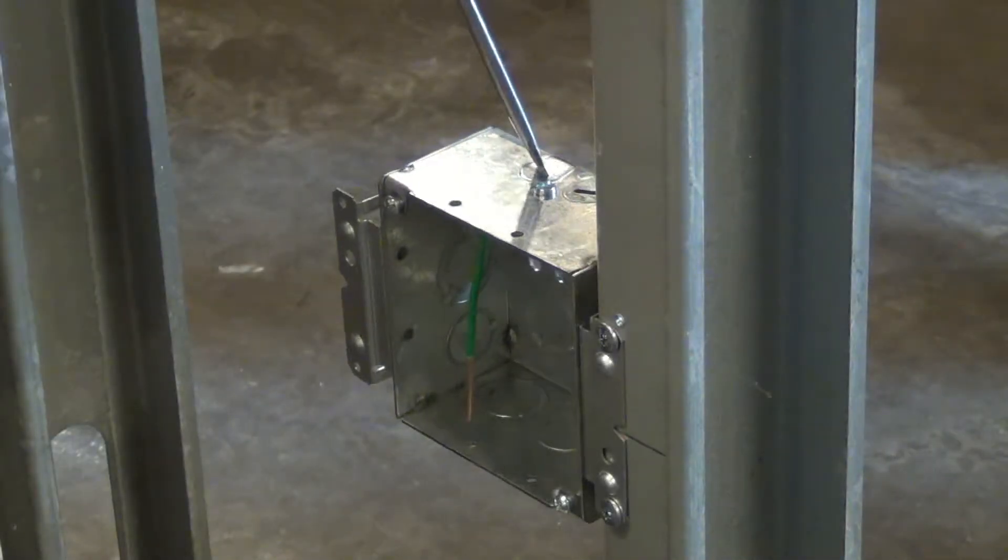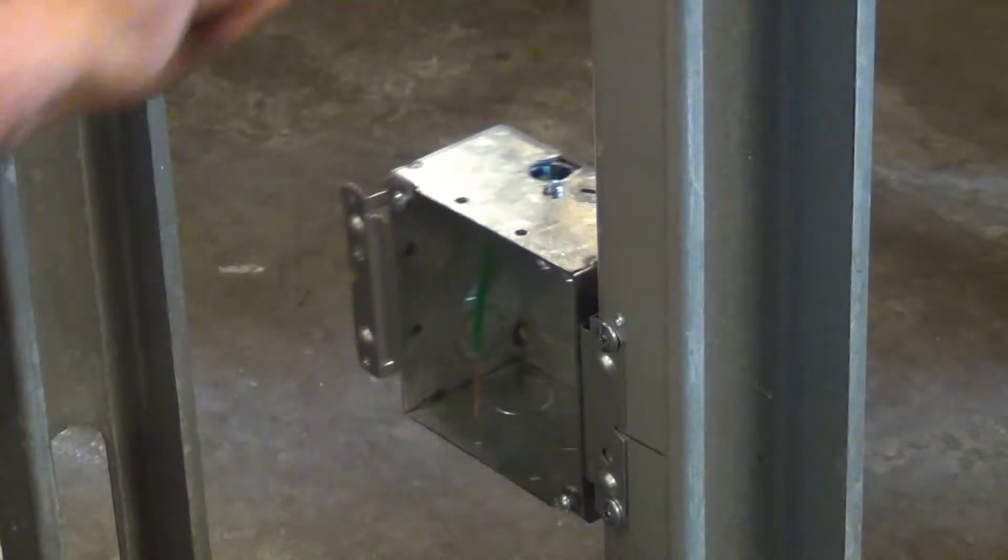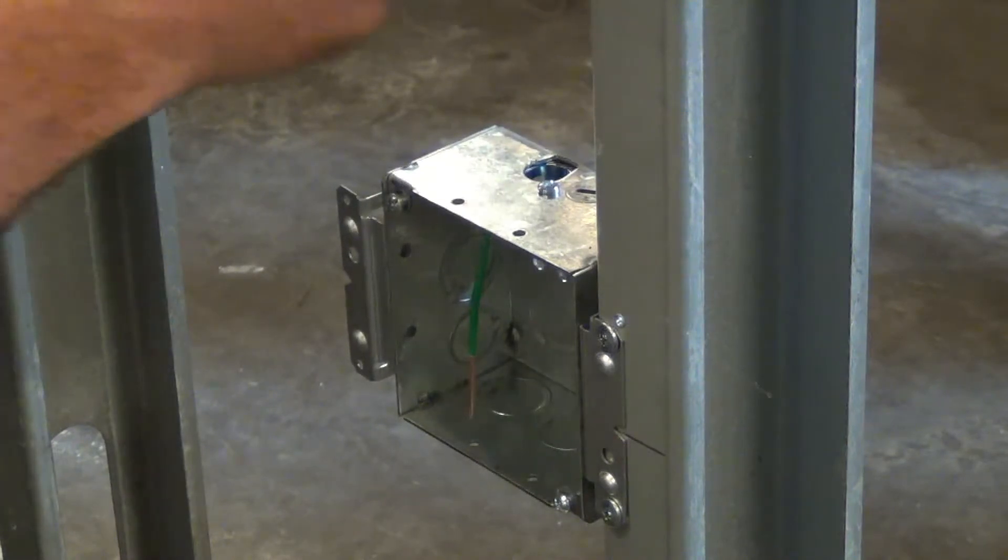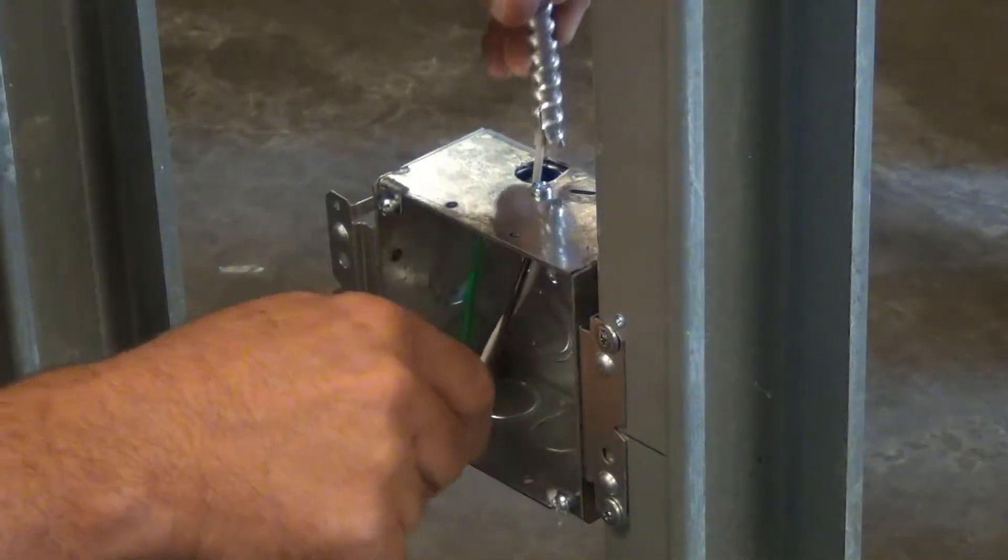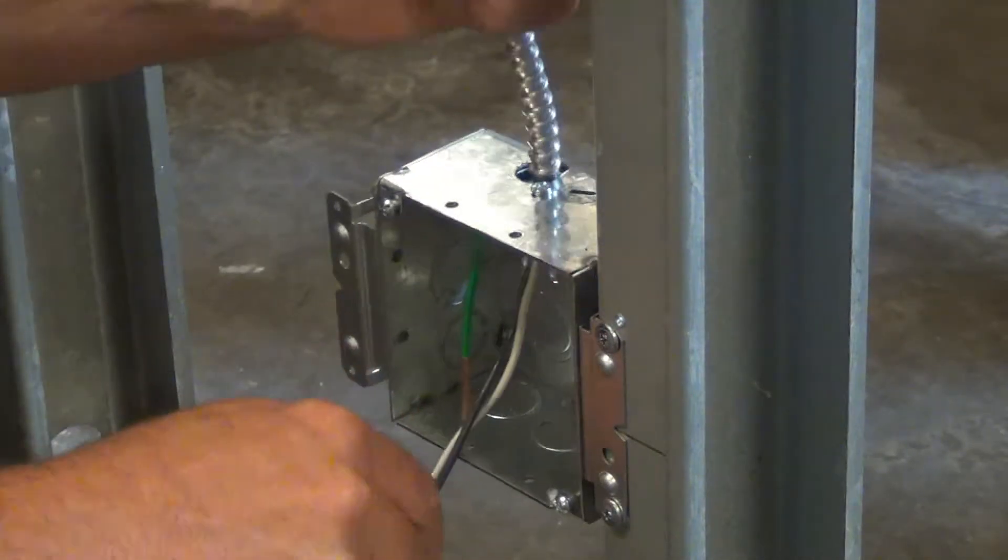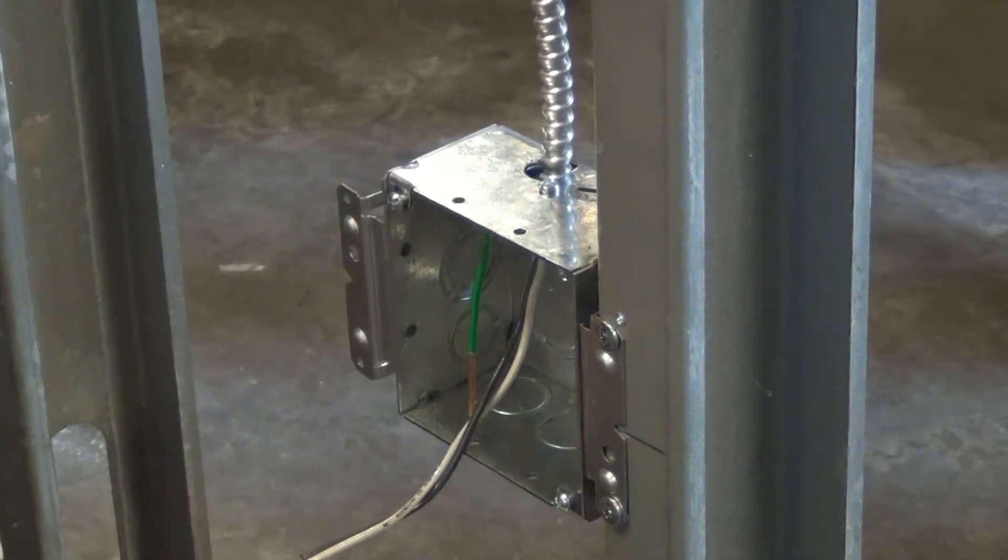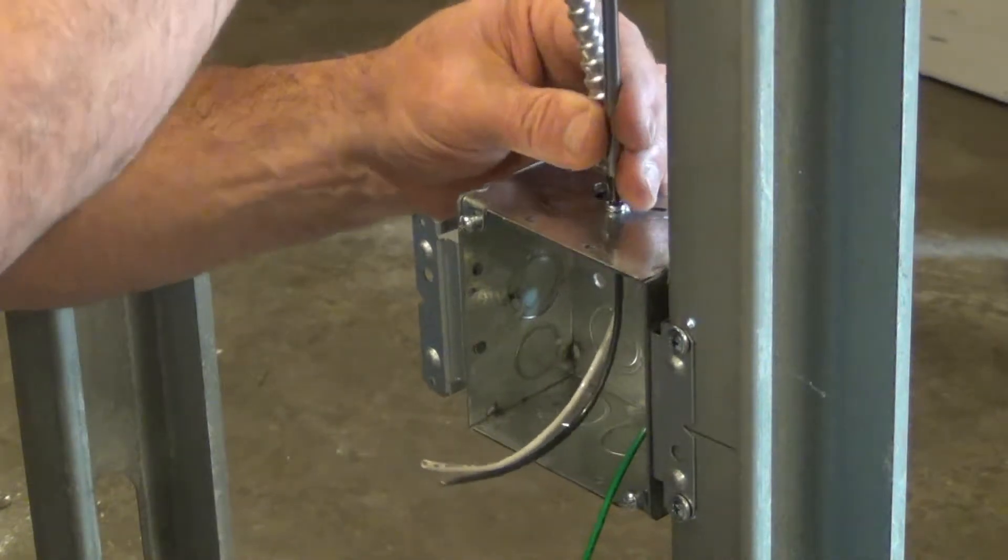To use a STAB-IT box, first remove one of the pear-shaped pry-outs. Second, with the cable already stripped, run the loose wires through the open pry-out and into the box. Lastly, just push the cable into the connector until you feel it lock into place.